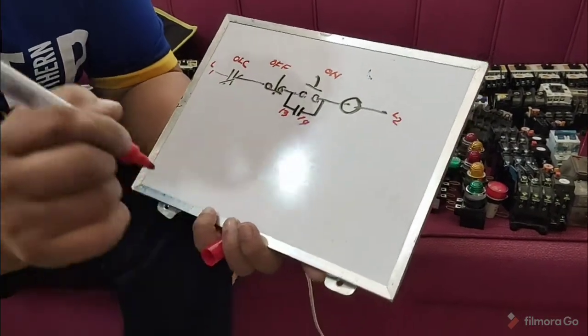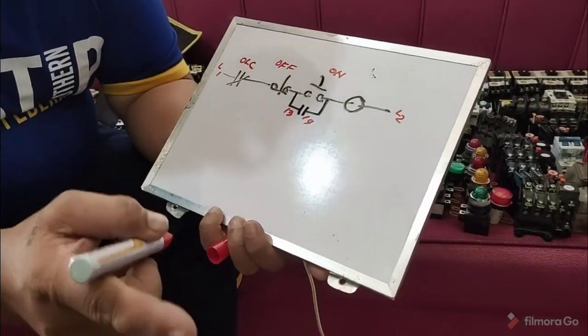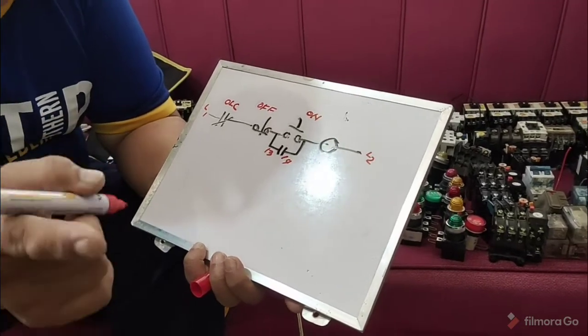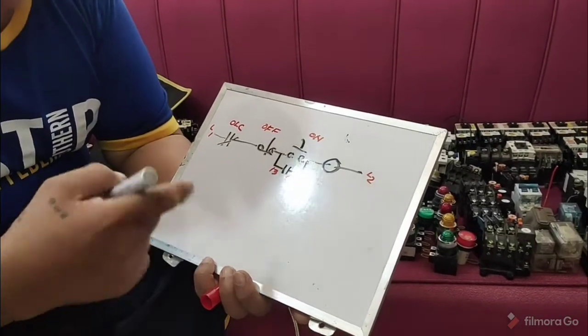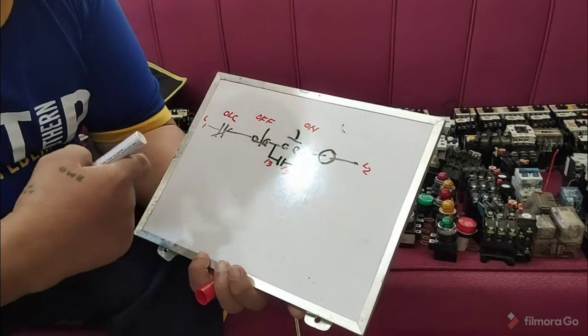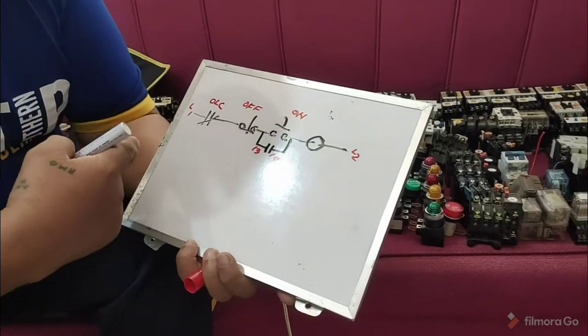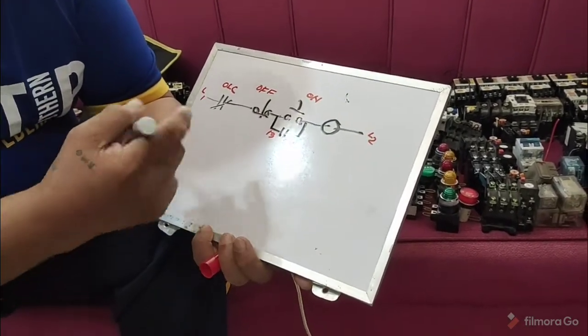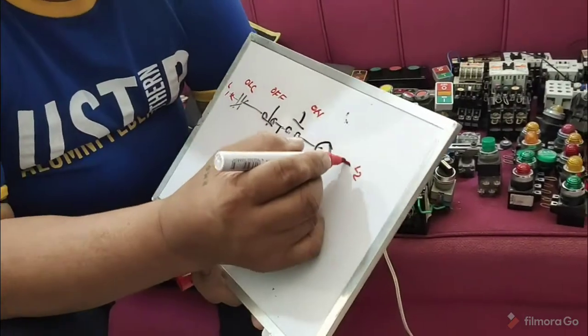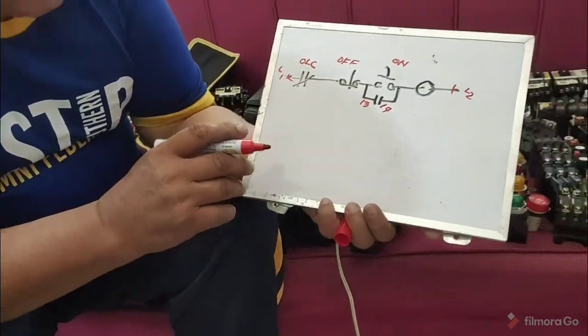Now remember, the control circuit is always single phase. You will connect this after the circuit breaker of your power circuit. If that is 3-phase, then you connect line 1 to line 2, this portion here. So this is the control circuit of the direct online magnetic starter.